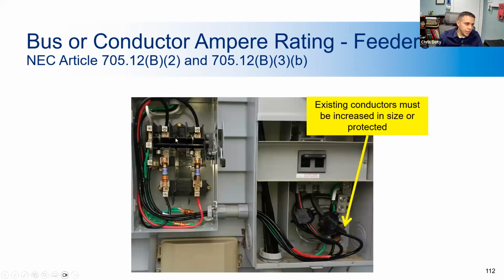And so here's a real life example of the previous slide. So you can see the interconnection on the load side of the 200 amp breaker in an apartment where the apartment panel didn't have a main breaker, and you have the meter pan with an integral disconnect. The existing conductors and possibly the bus bar downstream can be strained by this additional current. So possible solutions include conductors and the bus bar being increased in size for the new additional current, or additional protection by adding an overcurrent device before the loads, such as a main breaker in the panel.